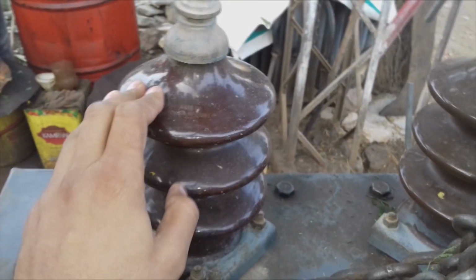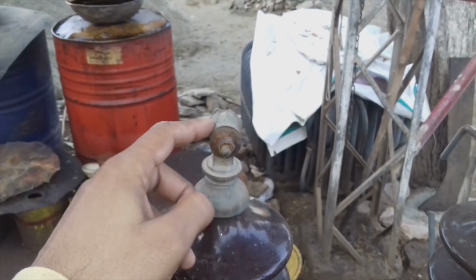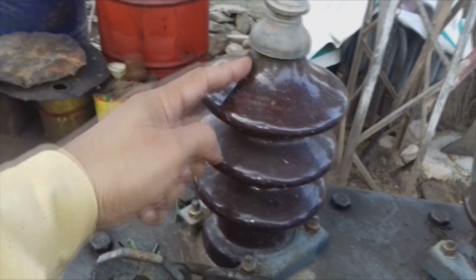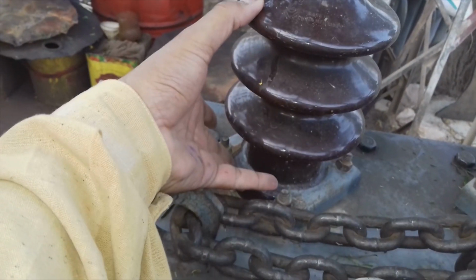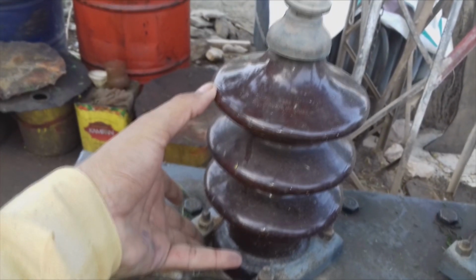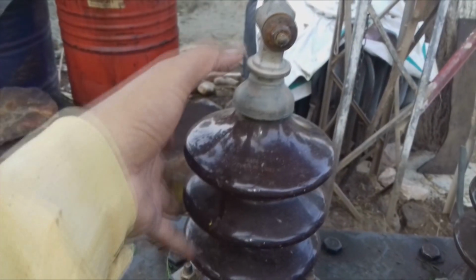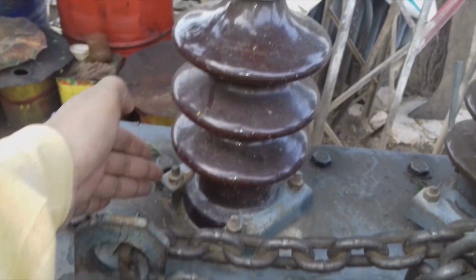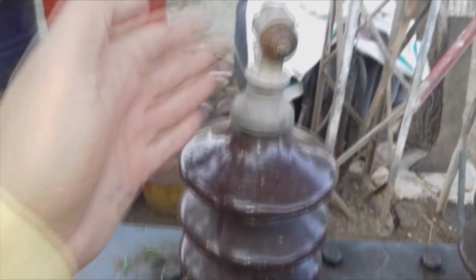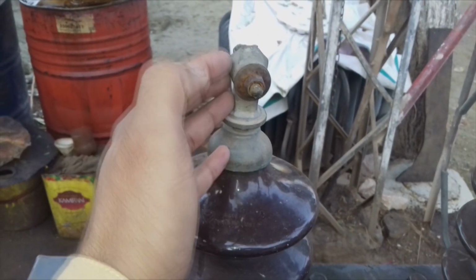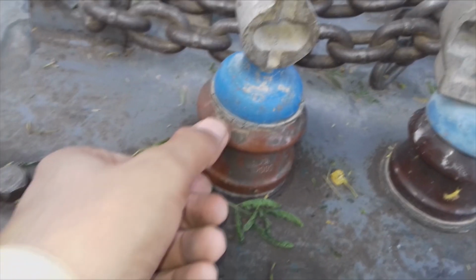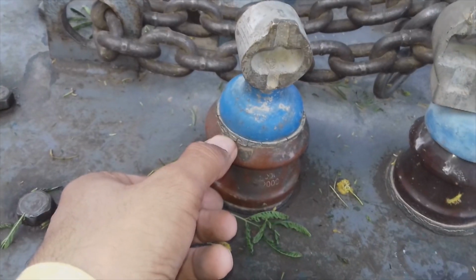Here are the primary terminals, the bushings, and this bushing you can see is for the HT side, and HT is connected through these bushings. This is an insulator actually, so water cannot enter, and also 11 kilovolt is applied, so it needs very good insulation, otherwise a corona could occur from the top side to the bottom of the transformer, which is of course grounded. These are the secondary bushings. As you can see, the insulation level is very much smaller compared to primary.